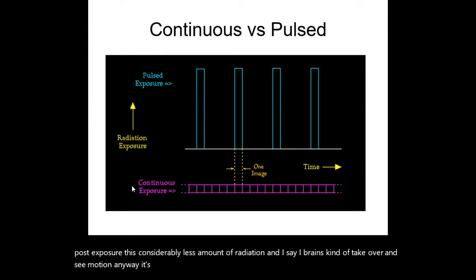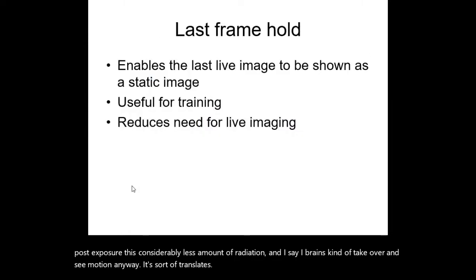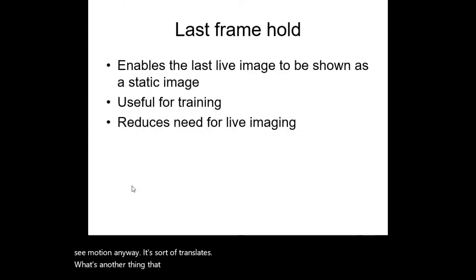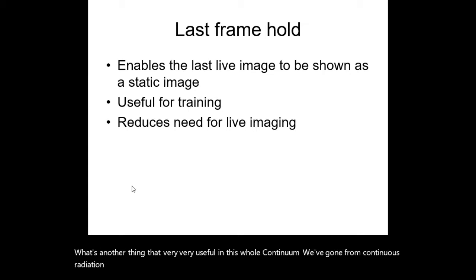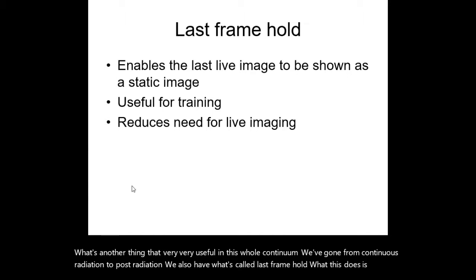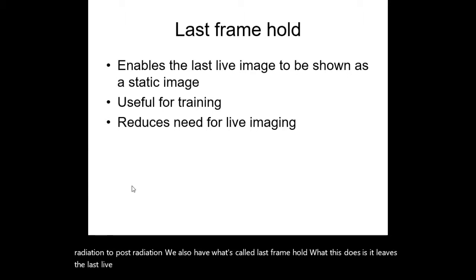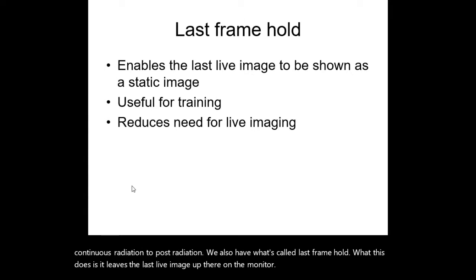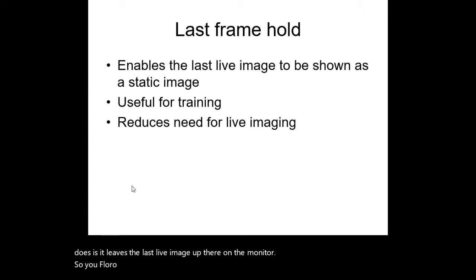It sort of translates. Now, what's another thing that is very, very useful in this whole continuum? We've gone from continuous radiation to pulsed radiation. We also have what's called last frame hold. What this does is it leaves the last live image up there on the monitor. So you fluoro, it goes beep, beep, beep. You take your foot off, and that last image freezes on the monitor. Sometimes that's all you need.